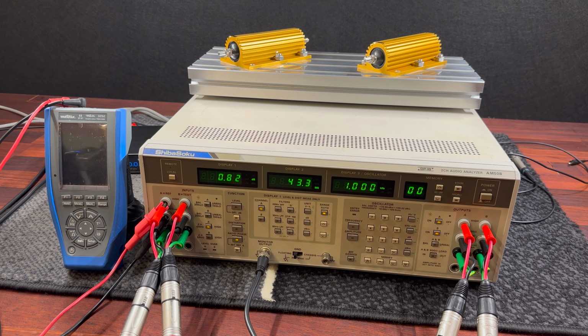So if we go to, say, 45 degrees phase, looking good. Go up to 90. Pretty much bang on also. Go to 120. 120 is good, and we'll take it right up to the edge of the range, so 179, and we're basically bang on. So we can go to, say, minus 90, and we are basically perfect. Minus 150. There you go. So I am very happy with this part of the analyzer. It didn't take much to adjust, but we know it is working correctly.